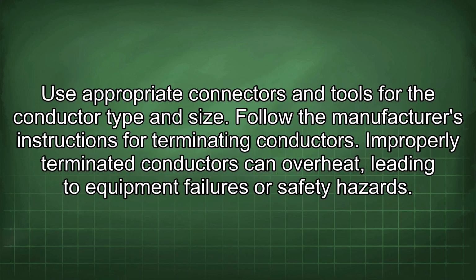Use appropriate connectors and tools for the conductor type and size. Follow the manufacturer's instructions for terminating conductors. Improperly terminated conductors can overheat, leading to equipment failures or safety hazards.